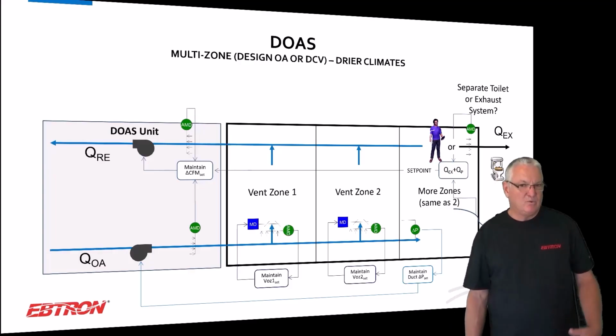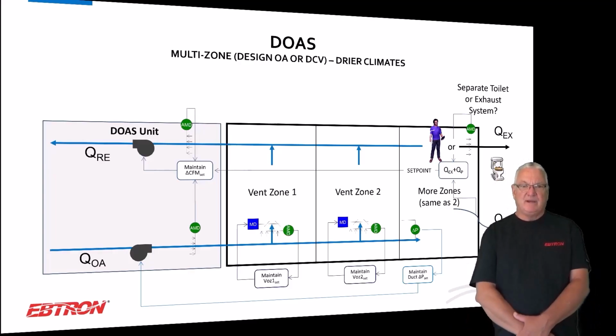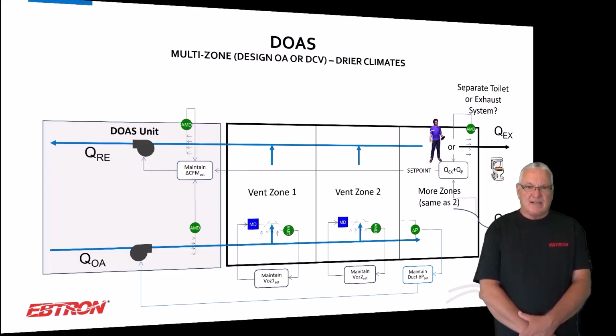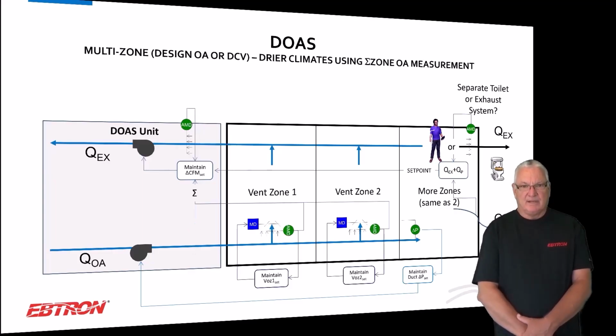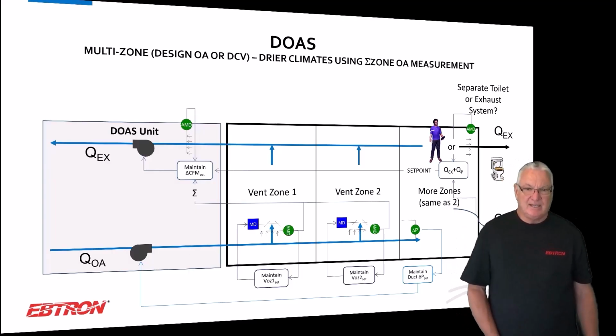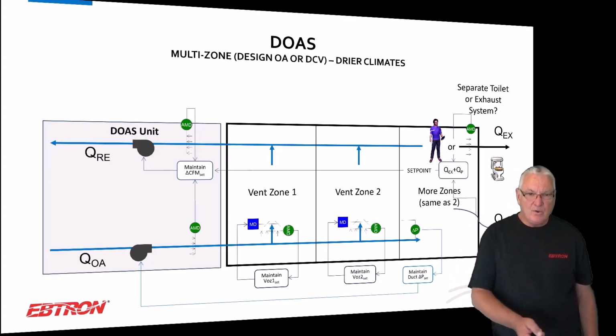We make specific equipment for these smaller ducts. Put in good measurement and set it up and walk away and be done with it instead of having to come back because your VAV box flow measurement drifted every year because the pressure sensors drifted every year. Okay, this is a fantastic application for our equipment. And I keep saying drier climates, but I mean, if you don't do anything, I'd like to see you at least do this.